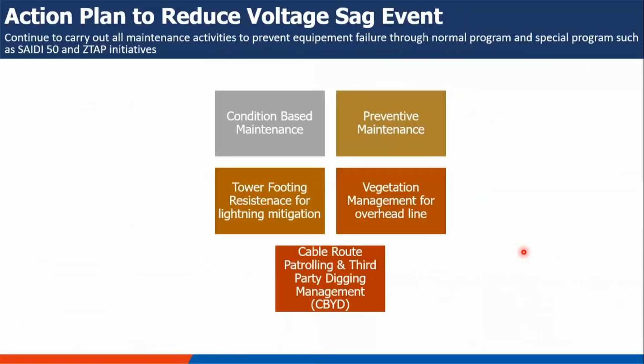Other things that TNB is doing to reduce voltage sags: as I said in the previous slide, the main causes are faults. So TNB has taken many actions to reduce faults, which are condition-based maintenance, such as PD mapping. Remember that cable is the highest contributor. Also preventive maintenance, tower footing resistance, vegetation management for overhead line height, cable route patrolling, and third-party digging management, CBYD. These are all the things TNB does to reduce faults, thus reducing voltage sag occurrences and severity. This is in line with TNB's SAIDI 50 and ZTAP initiative.